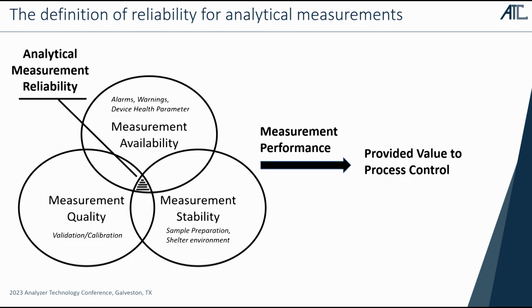So what I define as reliability is a combination of the availability of the device, which we can track with alarms and warnings and the internal device health parameters; the measurement quality, which we prove with frequent validation and, if necessary, calibration; and measurement stability, which is what I call the sample preparation status and the shelter status. And all of that influences the reliability of analytical measurement, and this is in the end the measurement performance, and based on that value we provide it to process control.